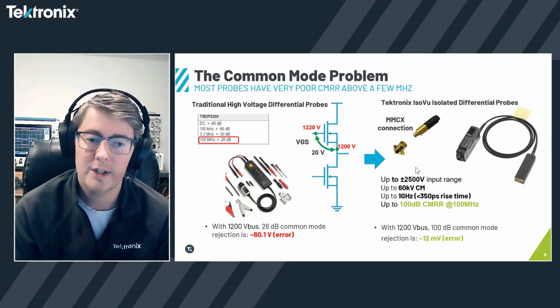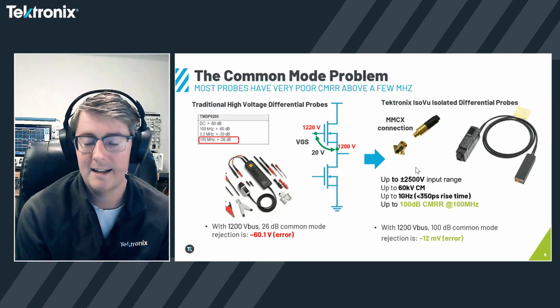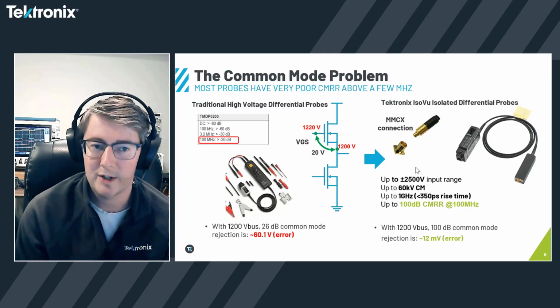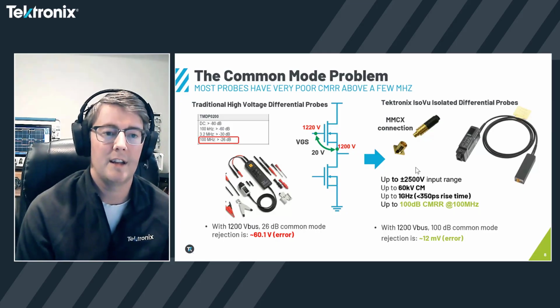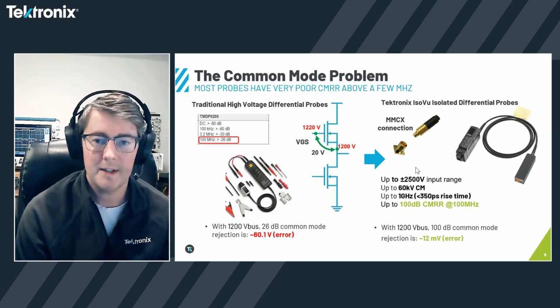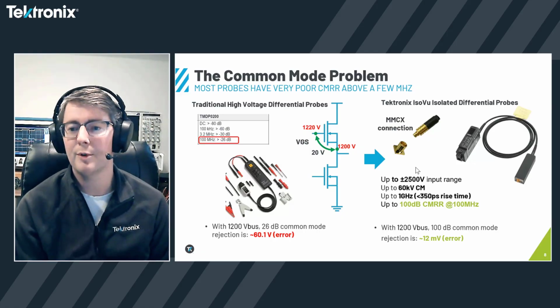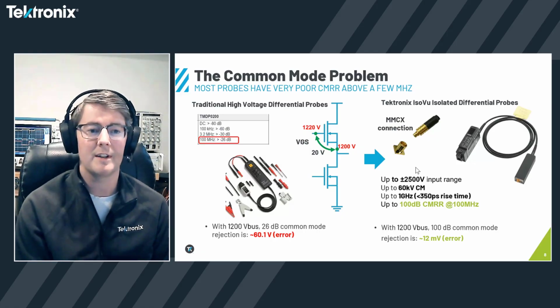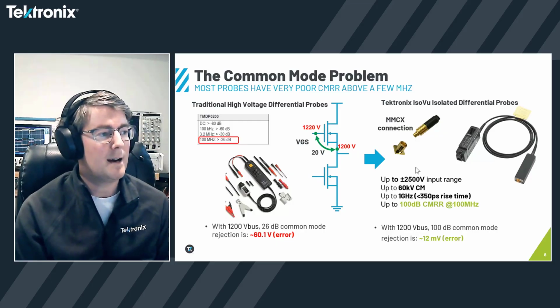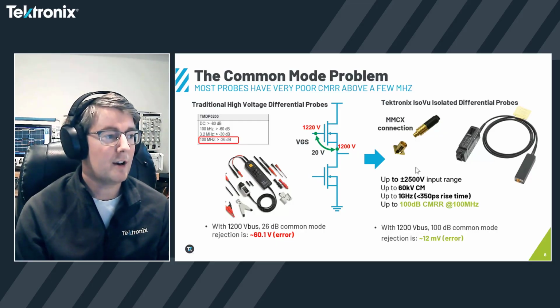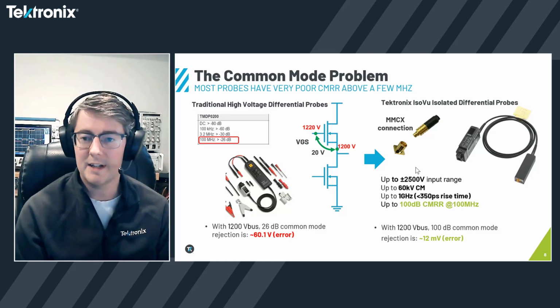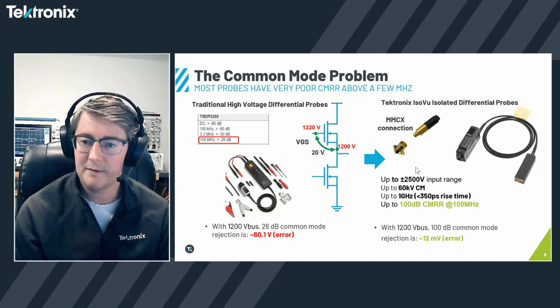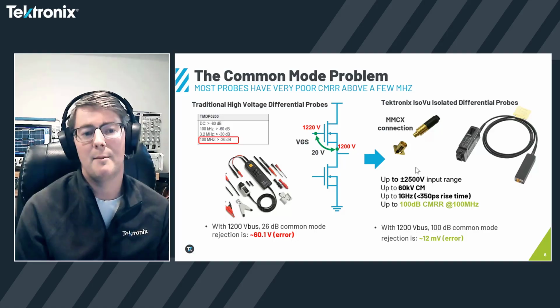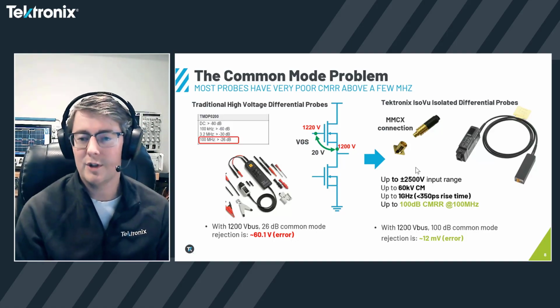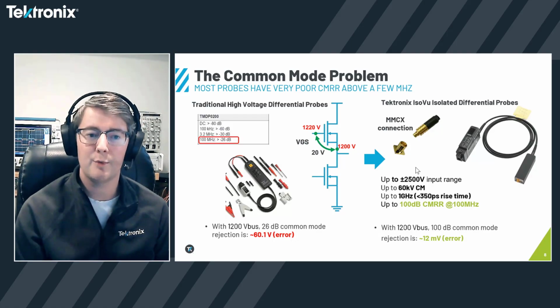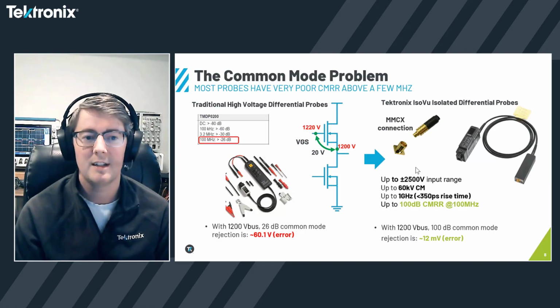Another challenge when talking about high side double pulse measurements is the effect of common mode interference and the ability for differential probes to reject that common mode interference. As you probably know, there are high voltage differential probes in existence that have lots of differential voltage range, but generally speaking, traditional differential probes have a challenge with what's called common mode rejection.